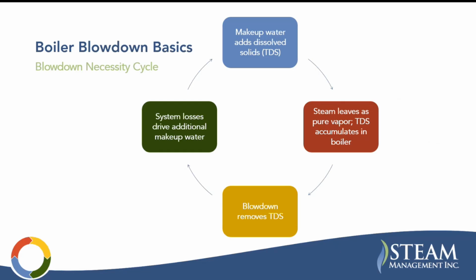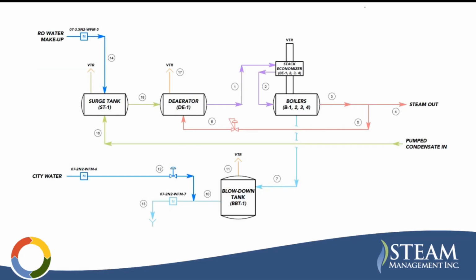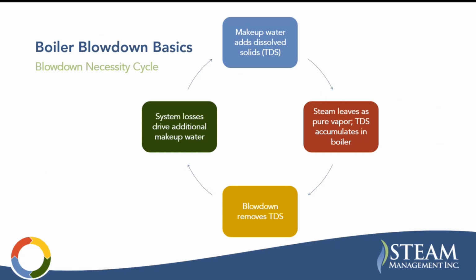This is the blowdown necessity cycle that I've made up. So we have makeup water adds dissolved solids to the system, typically abbreviated as TDS, total dissolved solids. Steam leaves the boiler as pure vapor, and TDS accumulates in the boiler. So as the boiler generates steam, all the steam leaves those impurities behind, and they start to concentrate in the boiler. Blowdown removes that TDS. So it is a stream of water rejected from the boiler to carry with it the total dissolved solids. As the system losses drive additional makeup water, more makeup water is introduced, and it continues to add dissolved solids, and the cycle continues.